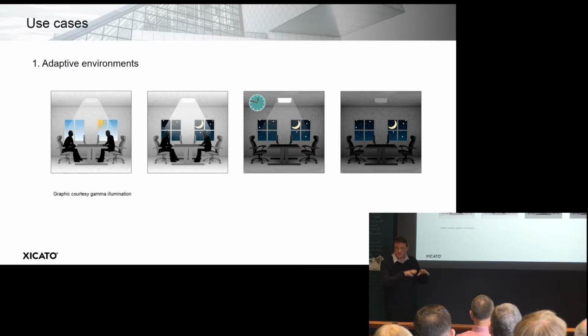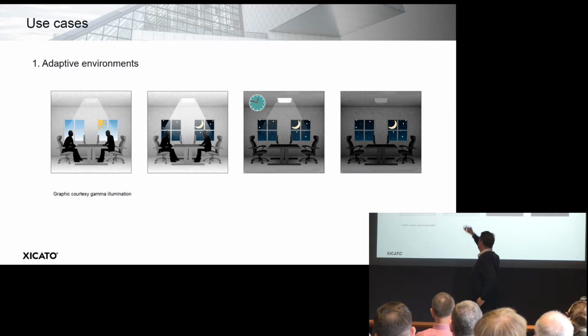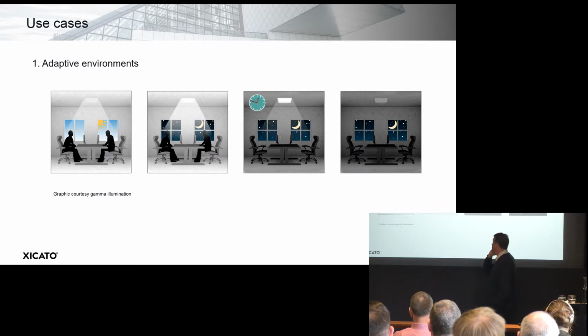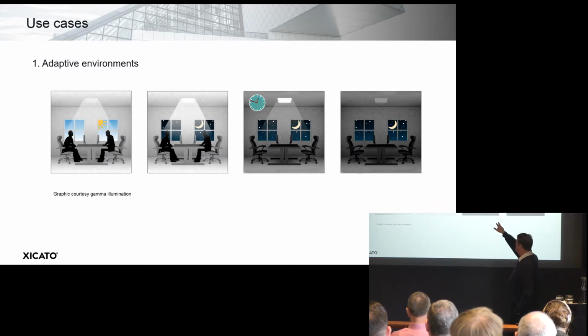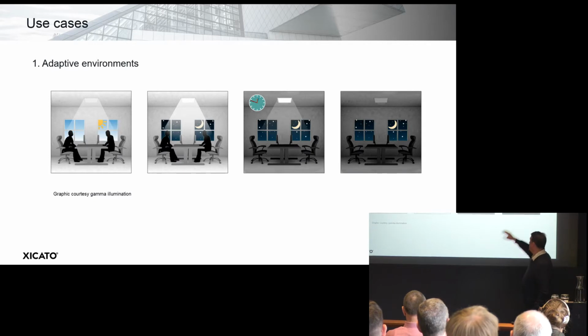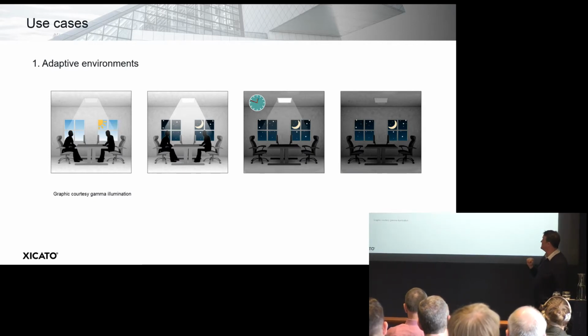So here you have smart lighting in an office environment, and there is daylight coming in, so the artificial lighting is tempered. You have the design illumination on the working plane, and energy saving because the lighting does not need to be on full. Here in a nighttime situation, movement is detected, so now the lighting is on full. You have the design illumination, but it's totally from artificial lighting. Here, the lighting is dimmed for a standby, hold-off period, for security reasons, and there's no one present. Then after that period, the lighting is completely off for maximum energy saving.